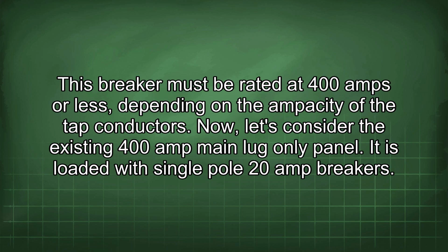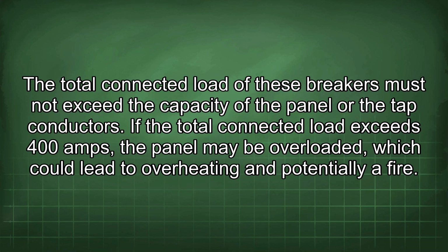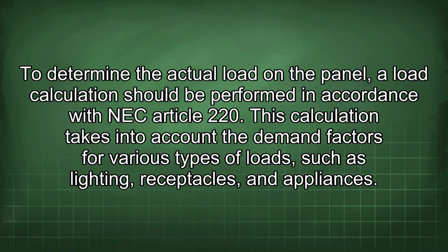Now, let's consider the existing 400 amp main lug-only panel. It is loaded with single-pole 20 amp breakers. The total connected load of these breakers must not exceed the capacity of the panel or the tap conductors. If the total connected load exceeds 400 amps, the panel may be overloaded, which could lead to overheating and potentially a fire.